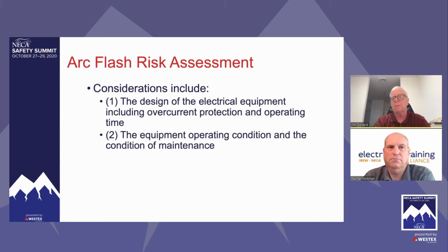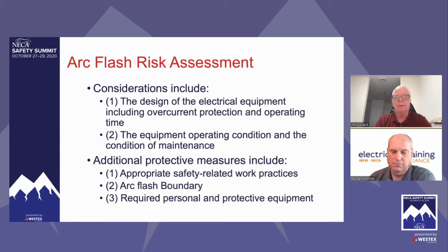We have to look at that upstream overcurrent protective device. We have to make sure that the men and the women in the field understand and know the difference between a standard molded case circuit breaker, an inverse time type device, a molded case circuit breaker with an adjustable instantaneous, an electronic trip molded case circuit breaker, an insulated case circuit breaker, and a low voltage power circuit breaker. We have to make sure that they understand the typical clearing times for those devices, which ones have an instantaneous override, which ones don't, and the maintenance requirements for those, and how to determine operating condition.